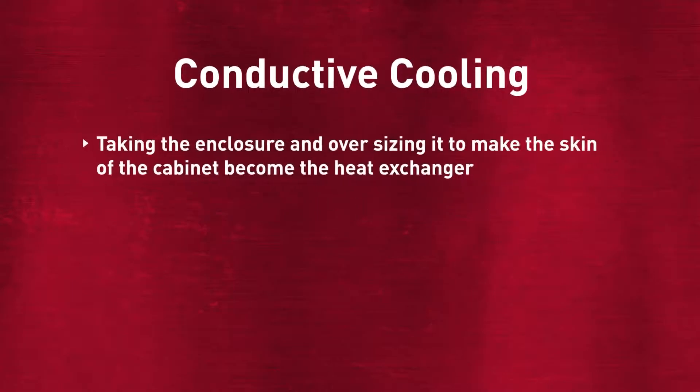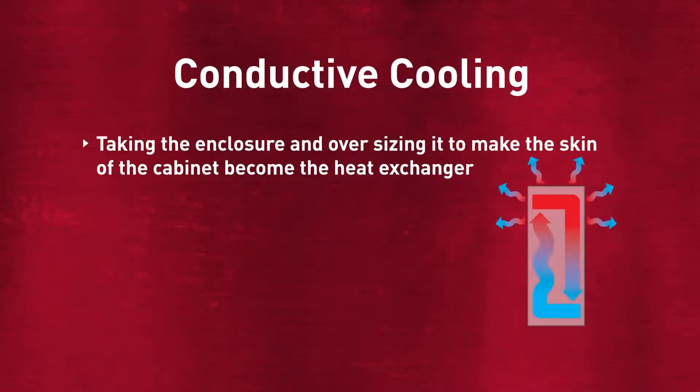The other type of cooling is conductive cooling. Conductive cooling is literally taking the enclosure and oversizing it to make sure that the skin of the cabinet becomes the heat exchanger. This only works in situations where you can allow the temperature inside the cabinet to be warmer than the outside temperature.